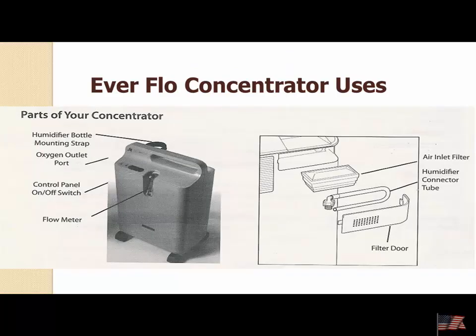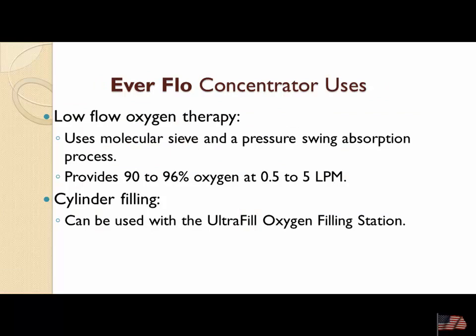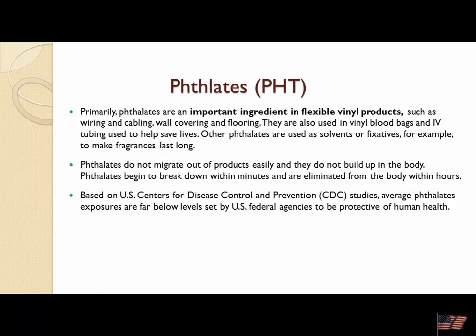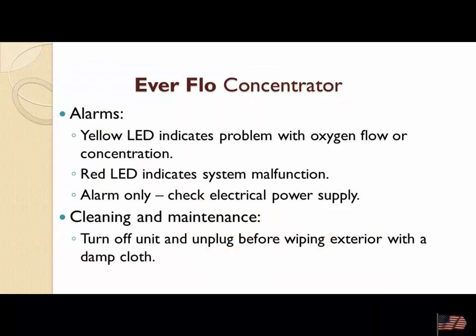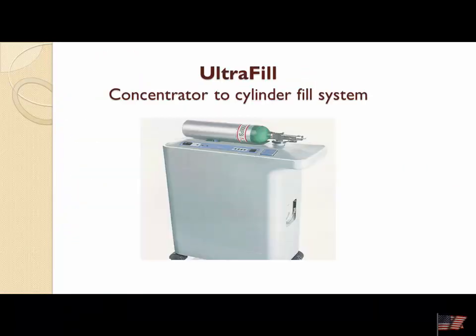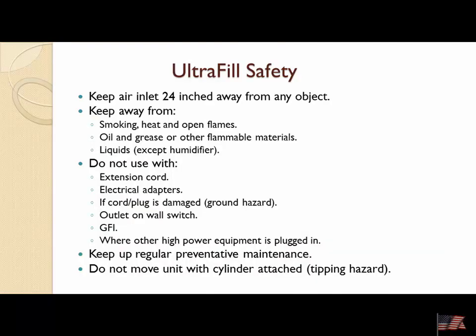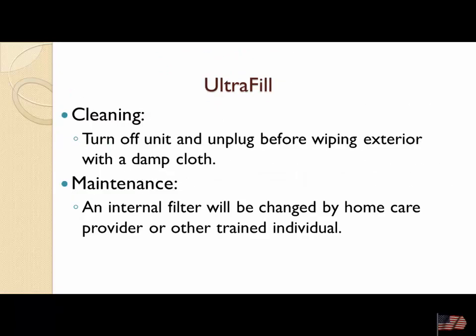And there's just another example of a concentrator that you end up having. There are some specific ones, and this is the one I wanted to show you. You can actually have it so that the concentrator fills the cylinder, which is kind of nice. So then they can take the cylinder if they need to go to the mall and they have some oxygen with them, come back home and they can place it on this concentrator that not only they can hook up a nasal cannula to, but they can also refill that system. And I'm again skipping through these. You won't need to worry about them because we're not going to utilize them.